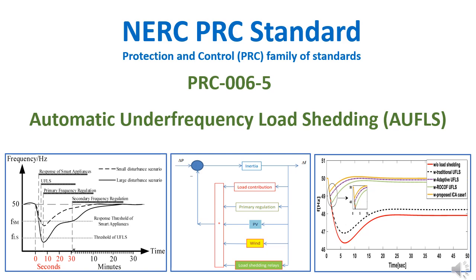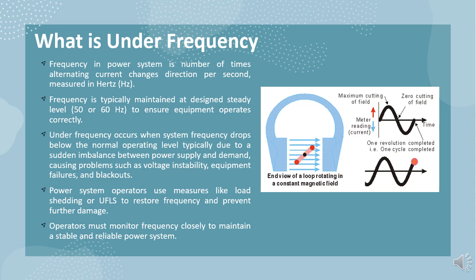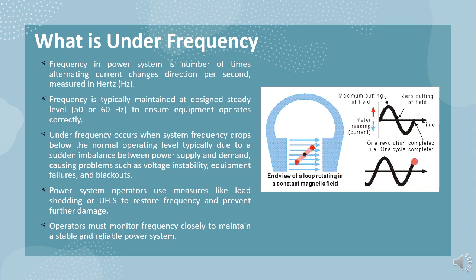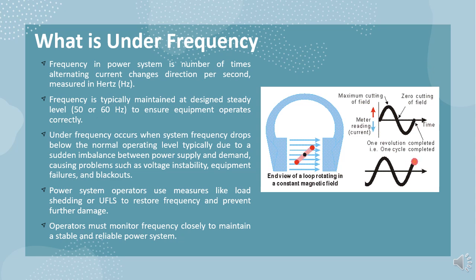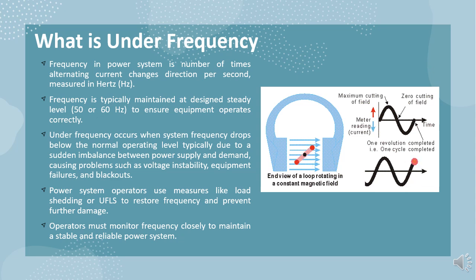Let's start by understanding what under-frequency means. Frequency in a power system is the number of times that an alternating current changes its direction per second, and it's measured in Hertz. To ensure that equipment operates correctly, the frequency is typically maintained at a design steady level of either 50 or 60 Hertz. However, under-frequency occurs when the system frequency drops below the normal operating level. This usually happens due to a sudden imbalance between power supply and demand, which can cause a range of problems such as voltage instability, equipment failures, and even blackouts.